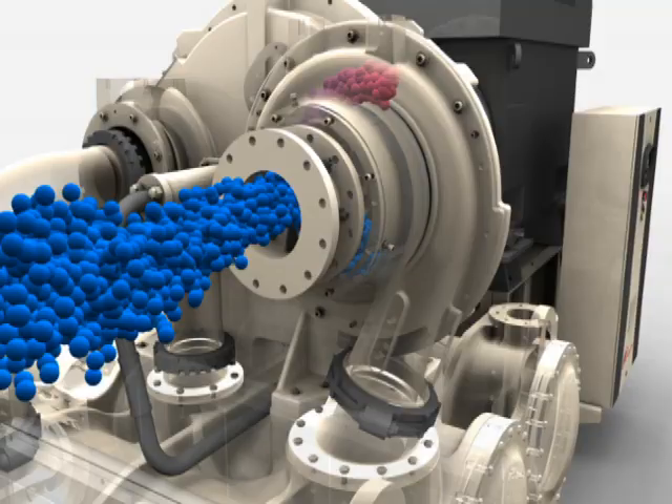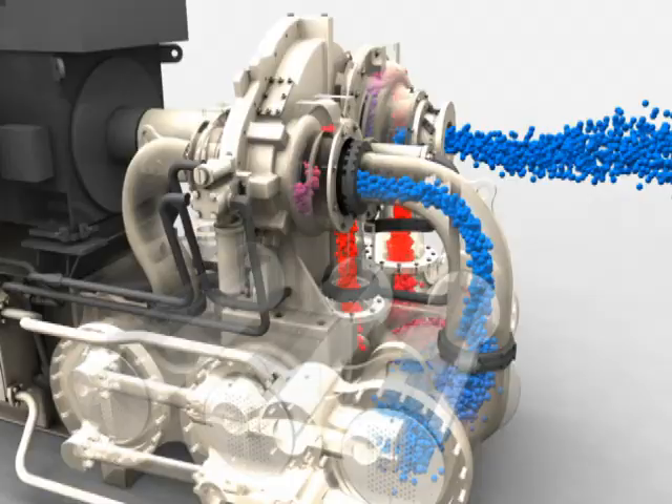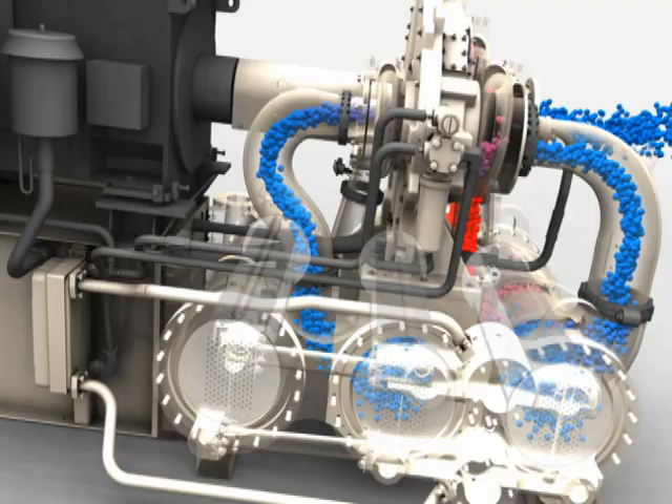After the air is accelerated by the impeller, it's slowed by a diffuser vane plate and shaped scroll. The precision-machined and corrosion-resistant vane plate minimizes turbulence and maximizes dynamic compression as the air velocity is decreased. The coolers knock moisture out of the air through temperature reduction.